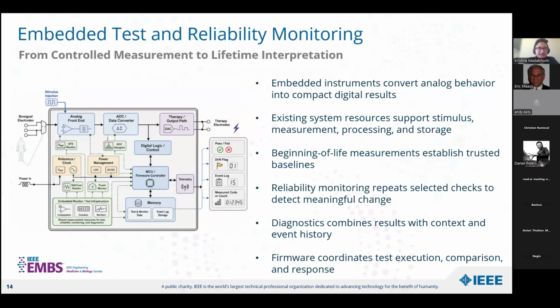So this diagram here shows the idea at a system level. The chip still contains the functional blocks we would expect. That is the analog front end, the data converters, the references, clocks, and any therapy, digital logic, and firmware control we need. The difference is that the selected observation and test capabilities are also built into this architecture. A monitor may sense supply current, compare a voltage, count cycles, inject some known signal, and capture the converter's response and verify it against an established baseline.